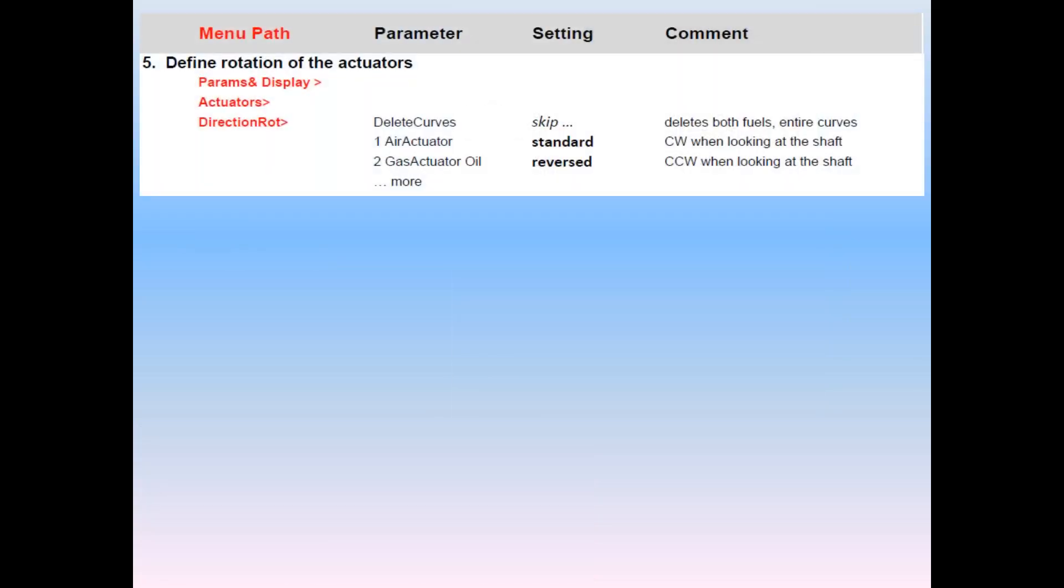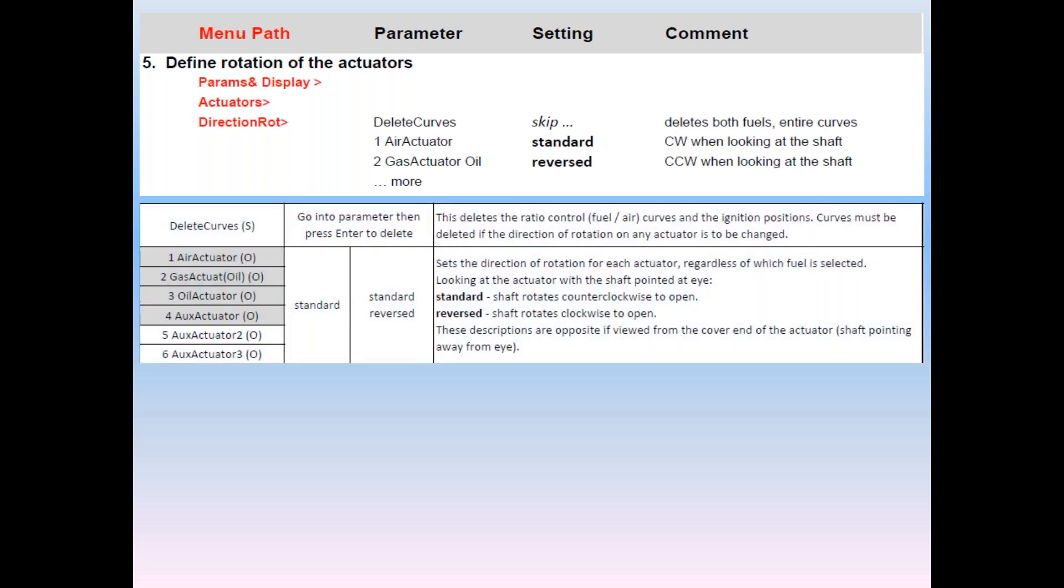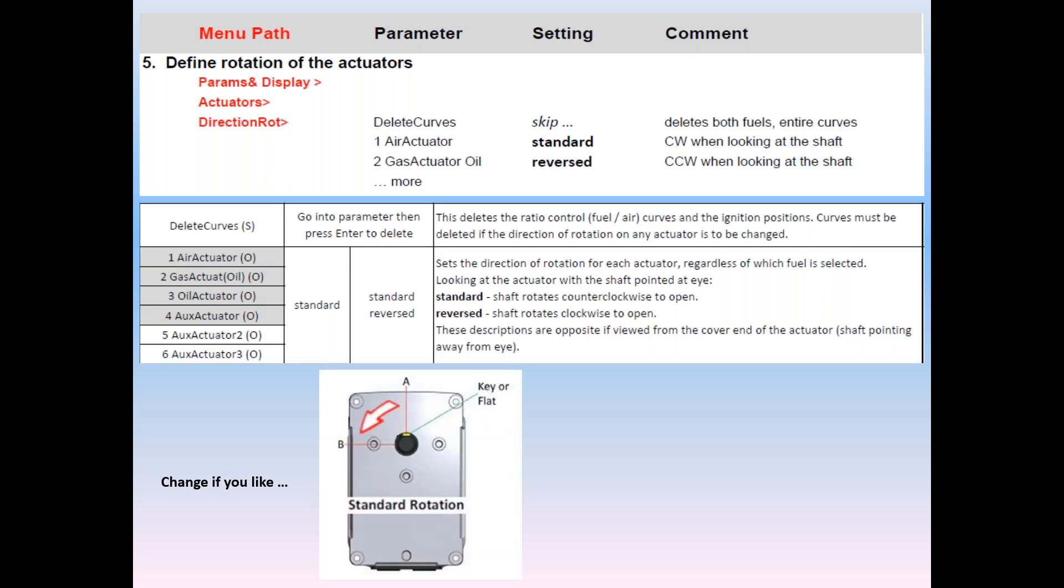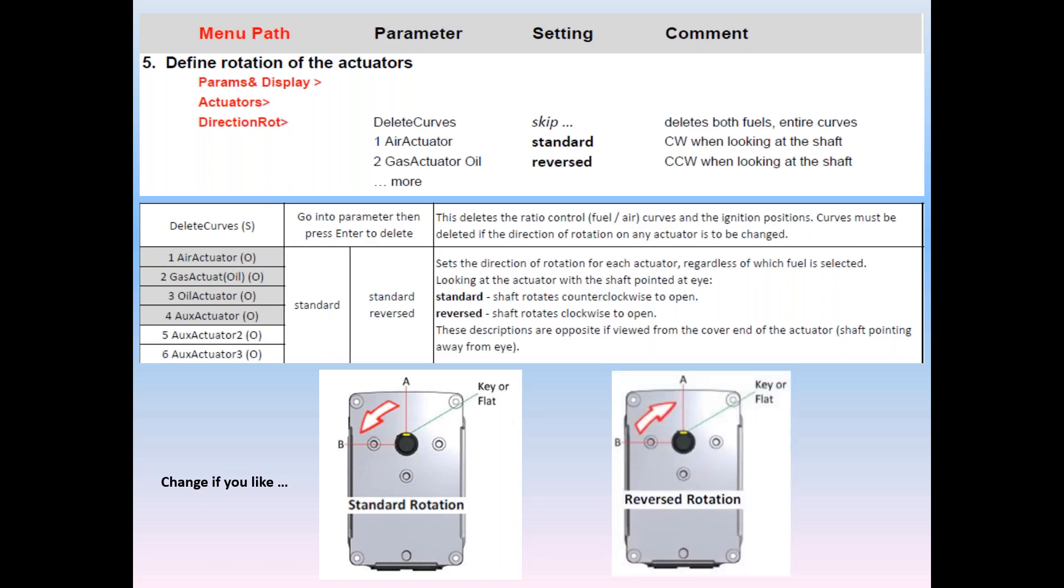Number five, rotation. Navigate to parameters and display actuator's direction of rotation, and then press enter. Now you can choose which rotation you want for each actuator. With the actuator facing you, that is, the shaft is poking you in the eye. Standard rotation is counterclockwise from straight up noon down to nine o'clock. Reverse rotation is clockwise, and it works from 9 a.m. to the 12 o'clock noon position. Kind of like a union shop, he says in the safety of a webinar class. Finally, be so advised. Direction of rotation must be set prior to ignition and curve settings. If you have those already set, and you need to change the rotation, you must select the first item in this list and delete the curves.